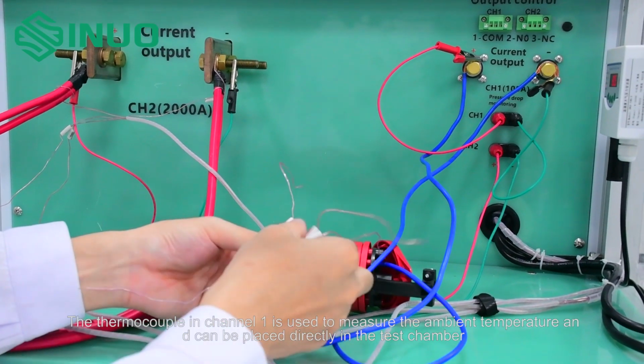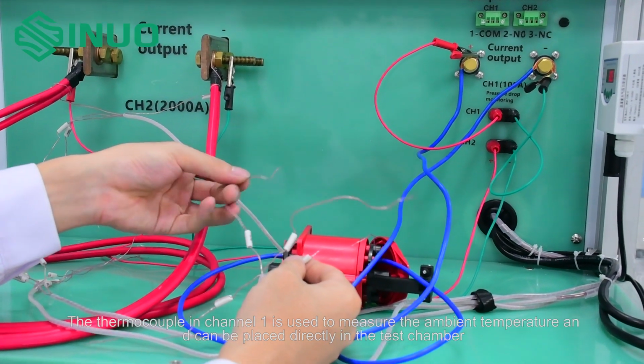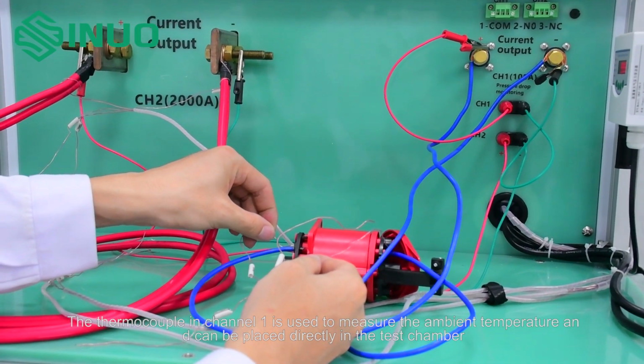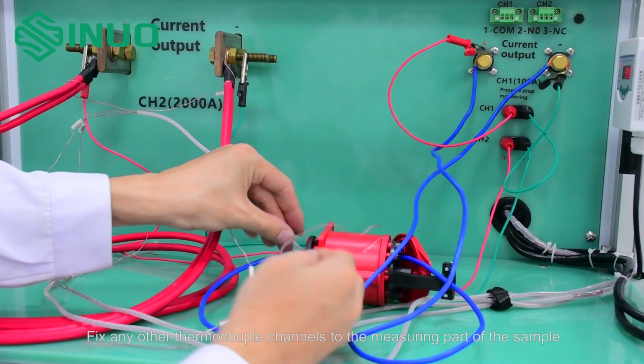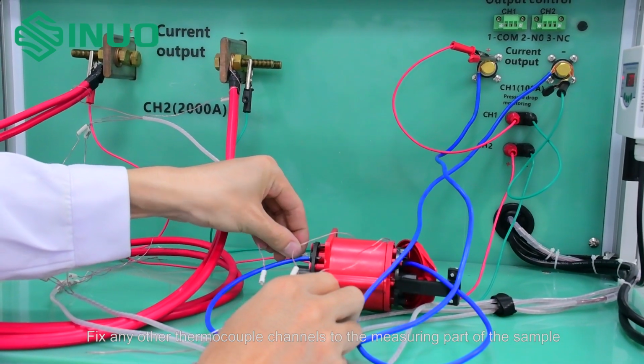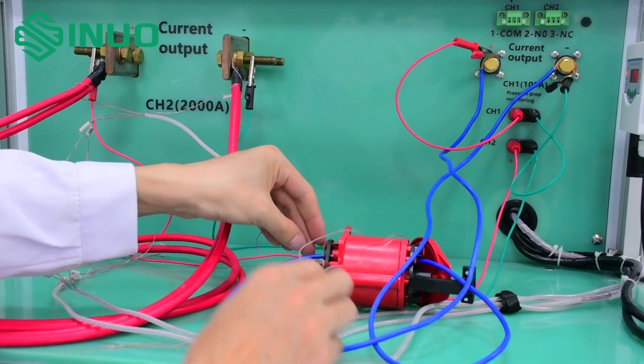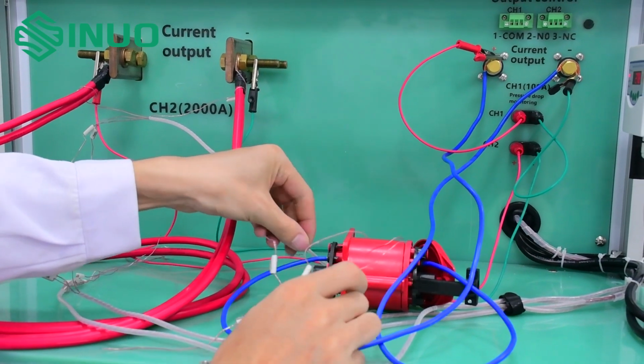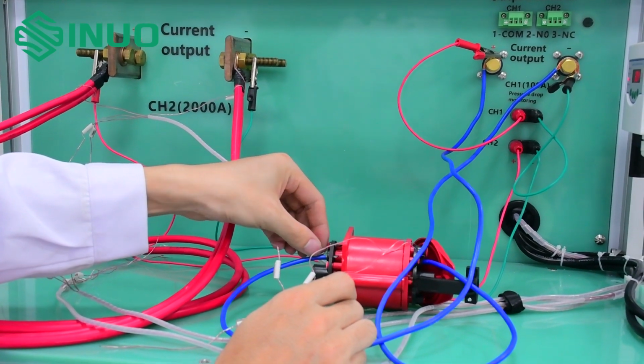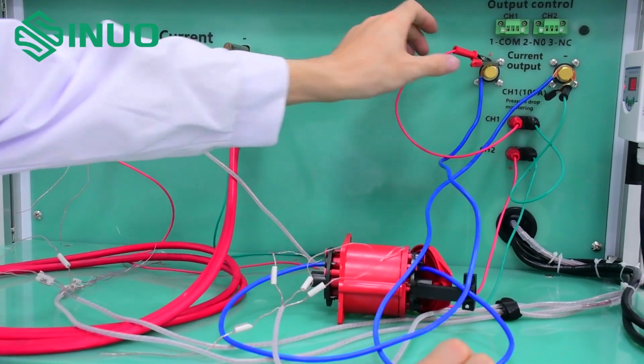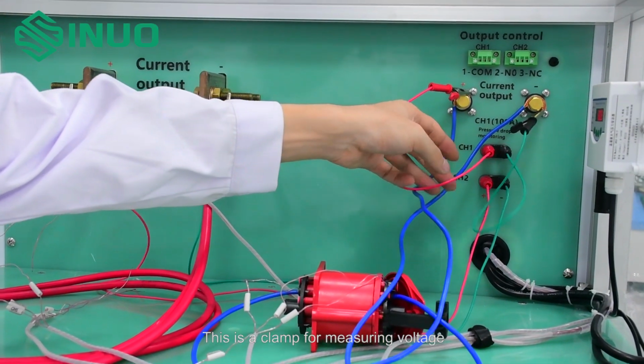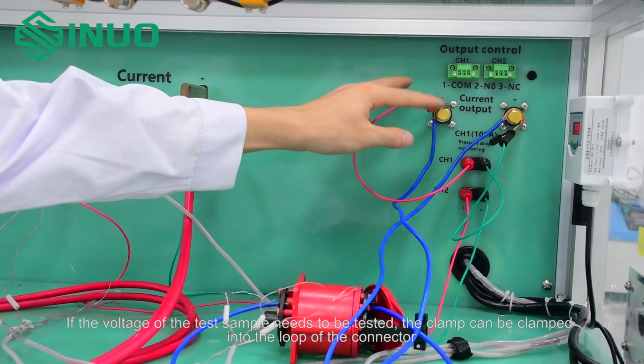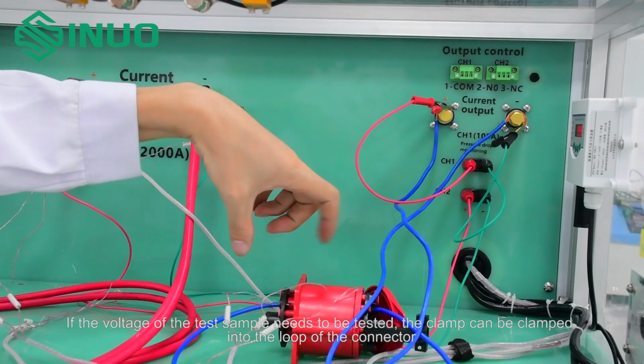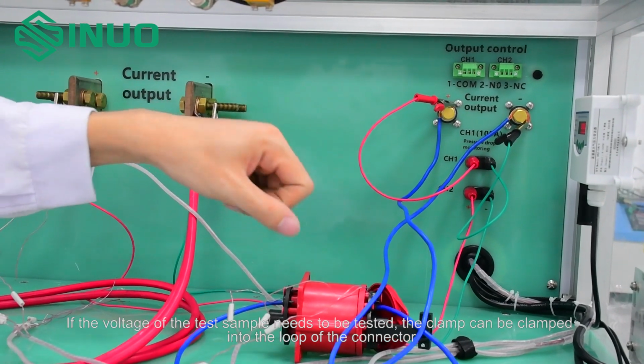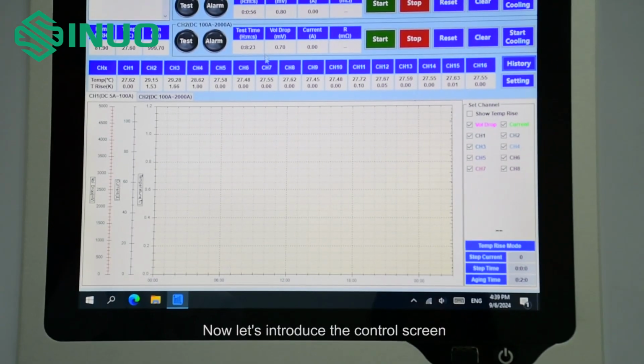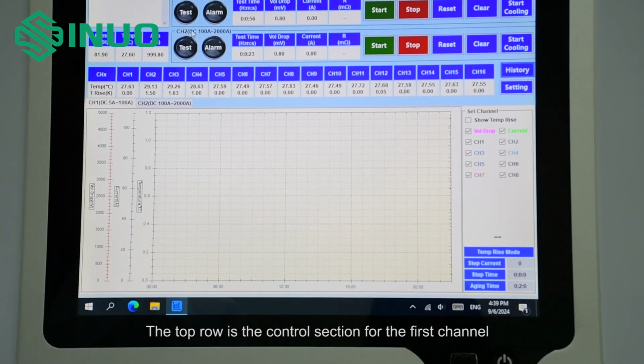The thermocouple in channel 1 is used to measure the ambient temperature and can be placed directly in the test chamber. Fix any other thermocouple channels to the measuring part of the sample. This is a clamp for measuring voltage. If the voltage of the test sample needs to be tested, the clamp can be clamped into the loop of the connector. Now let's introduce the control screen.